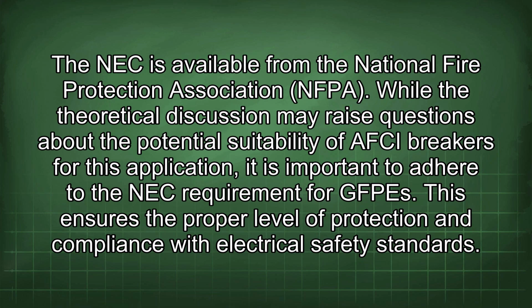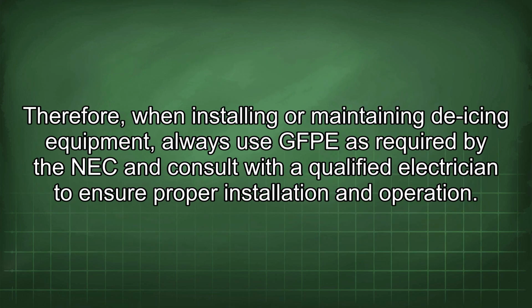While the theoretical discussion may raise questions about the potential suitability of AFCI breakers for this application, it is important to adhere to the NEC requirement for GFPEs. This ensures the proper level of protection and compliance with electrical safety standards. Therefore, when installing or maintaining de-icing equipment, always use GFPE as required by the NEC and consult with a qualified electrician to ensure proper installation and operation.